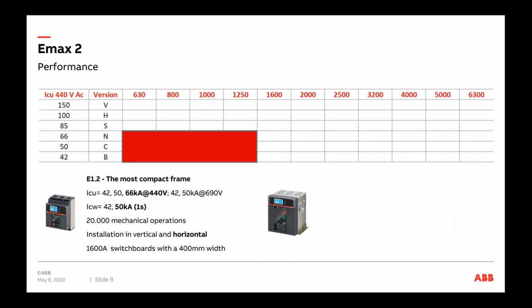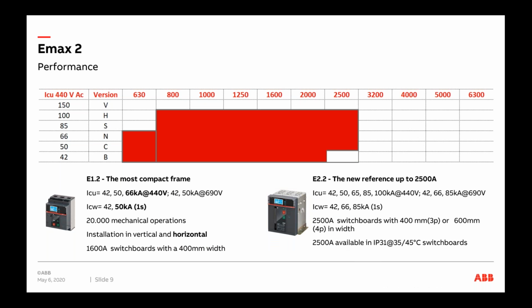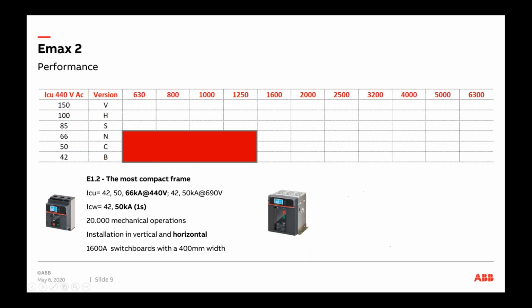Then we will speak about the first 2 breakers we look at from the range. One is the E1.2, which is the most compact range, and we also have a molded case circuit breaker we call the XT7. Previously, we had a breaker called T7. They're pretty much exactly the same size. The difference is that one is a molded case and one is an air circuit breaker. The protection levels are quite significant in this range as well. We can look at not only 1250 amps, 1600 amps, we look at 66 kA when it comes to that particular breaker.